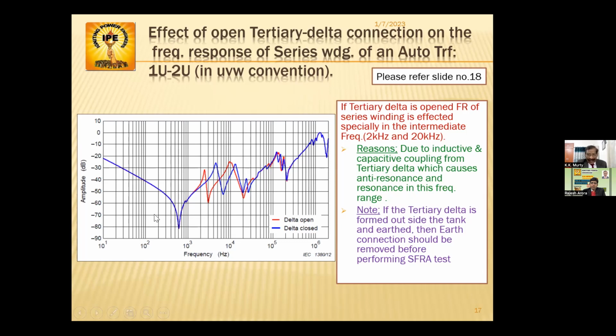The open delta curve is this red. This is because the tertiary delta is open. If the tertiary delta is open, the frequency range of the series winding is affected, especially in the intermediate frequency, that is 2 kilohertz to 20 kilohertz. This is 10 kilohertz, and this is the 20 kilohertz area.